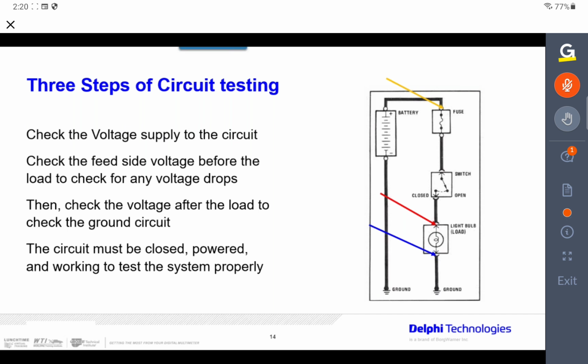What if it read 12 volts? Then I drop 0.6 volts across the circuit. I have a resistance, a drop there. That can be from corrosion, bad connection, or other things. So I would want to work my way backwards from the load to find it. When I find source voltage, but I didn't have source voltage on the other end of that one, that next step up would be my issue. So I would go back from after my switch, before my switch. If all of a sudden I had source voltage at my switch on the feed side, but on the side feeding over after my switch I had a drop in voltage at that point, I know my switch is the component I would need to replace. And the easy way to do it is jumper around that with jumper wires.